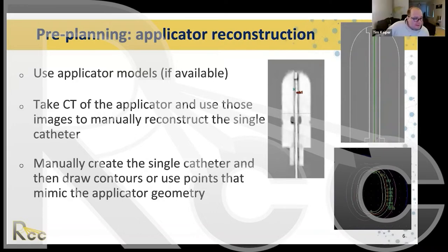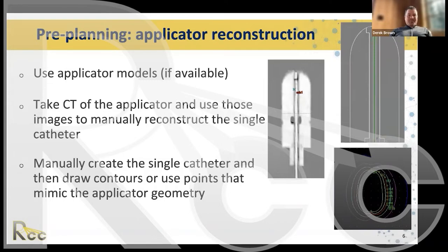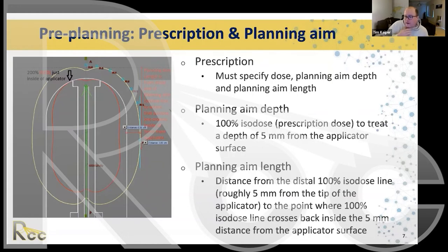We should use applicator models if available — some treatment planning systems have these embedded. We should take a CT of the applicator and use those images to manually reconstruct the single catheter. This CT image shows a cylinder inserted in a phantom with a dummy wire through the central catheter, which allows us to digitize — telling the treatment planning system where in three-dimensional space we can place seed positions.